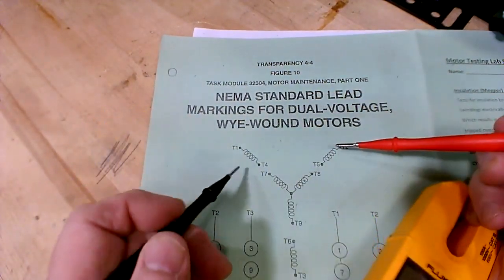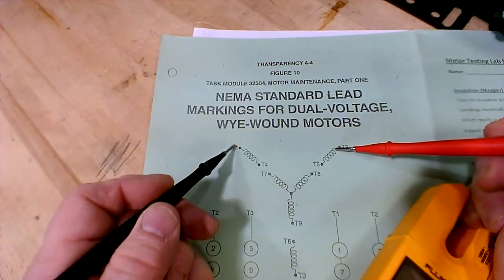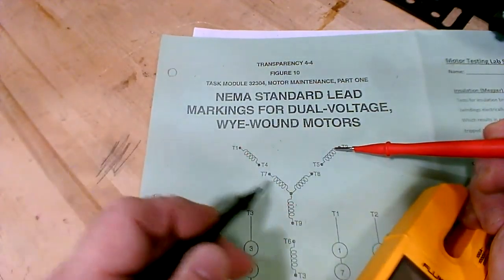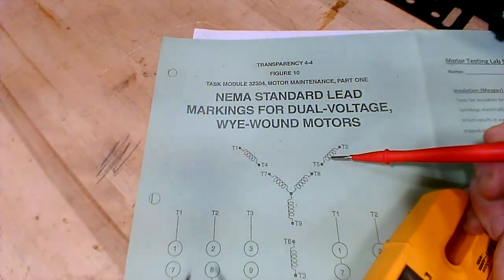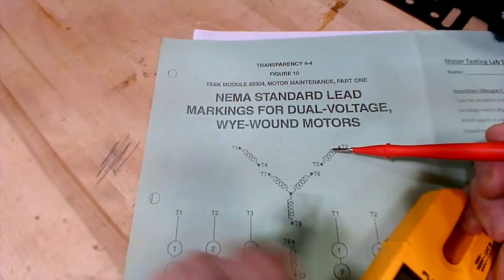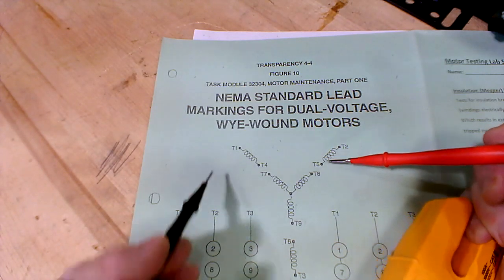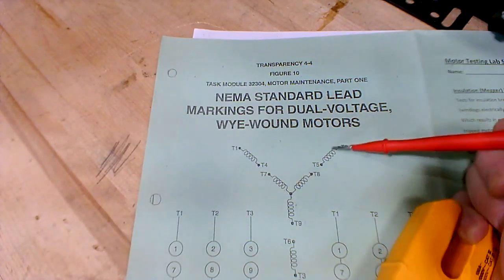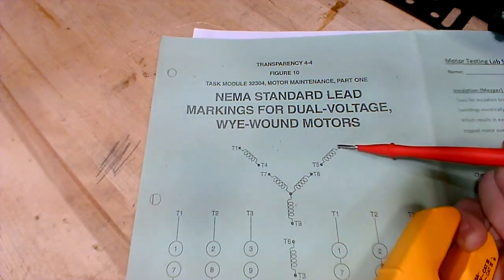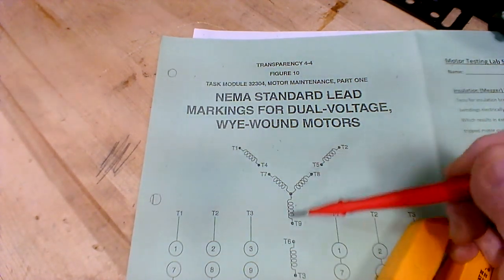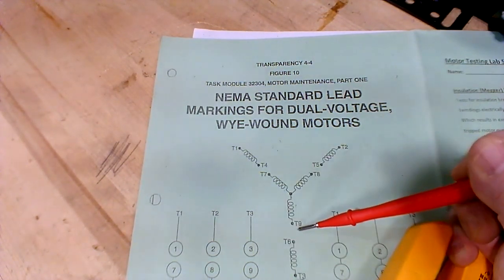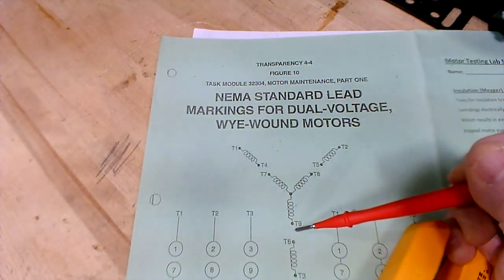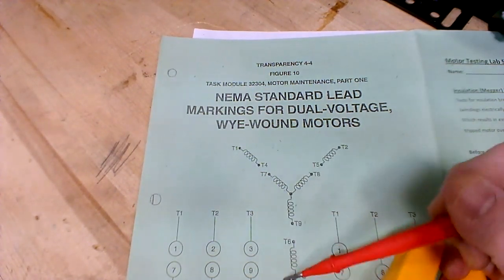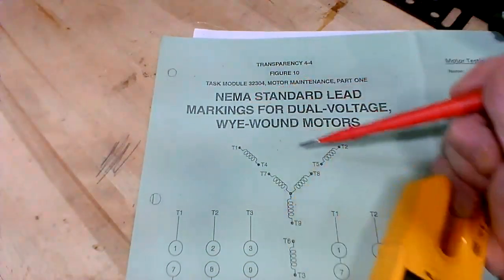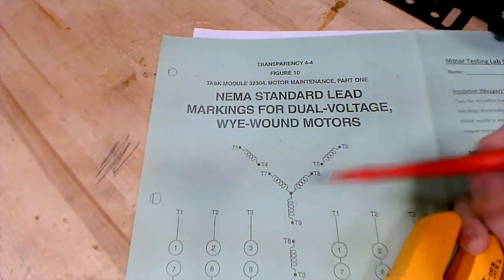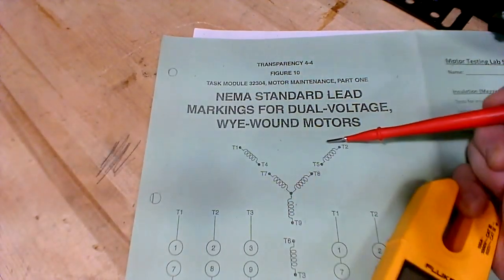And you're going to go from T1 to T2. When you do that, you're going to check continuity through this set of four windings. And that's going to tell you if you have a broken winding. Then you're going to check from 2 to 3. And that's going to get continuity internally through those three windings. That's going to tell you if you've got a broken winding in there somewhere, or a wire nut that's come off in the cabinet. So if one of your wire nuts pops off, it's going to show you that you have an OL, over limit, and you need to check the wire nuts first. And if they're good, then you've got a broken winding in there if it says OL.